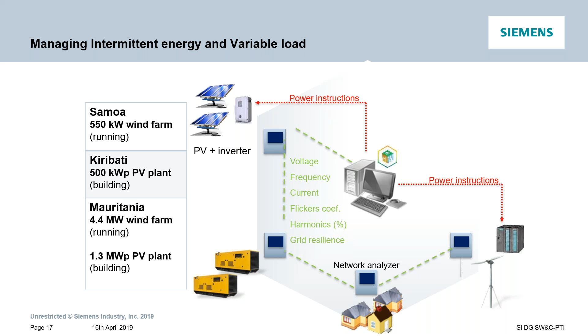Let me show this on a picture that's more meaningful for how to control it. We have a network analyzer looking at the actual load, then the inverters, and the PV farms or panels. The whole system is linked together in a metered, automated, computerized system that decides when to run the diesel more during high demand if solar or wind isn't sufficient to cover demand, and when to back off the diesel if there's excess solar or wind generation. If you have batteries, it also controls when to charge and discharge them.